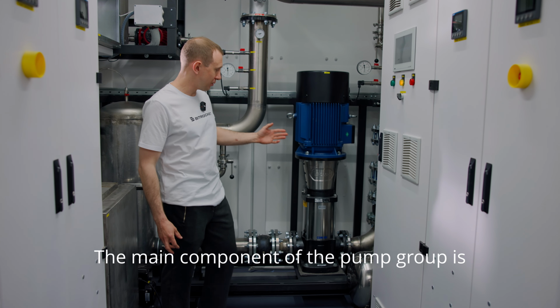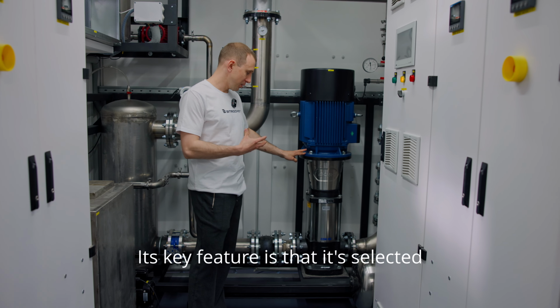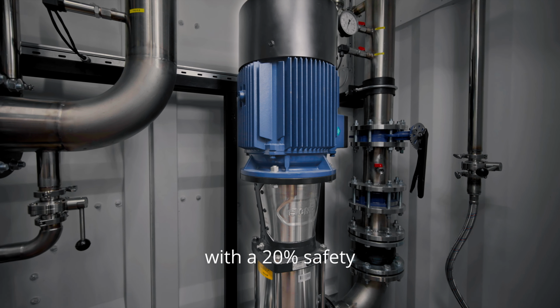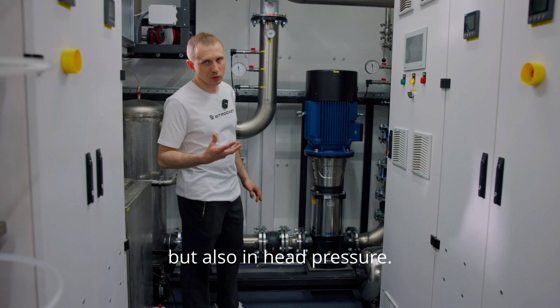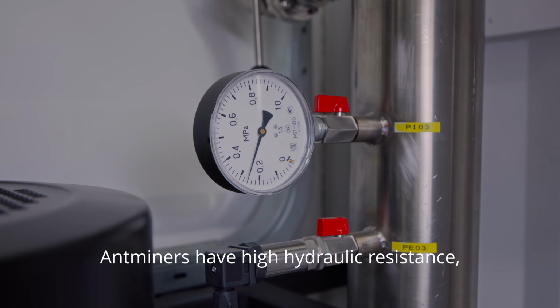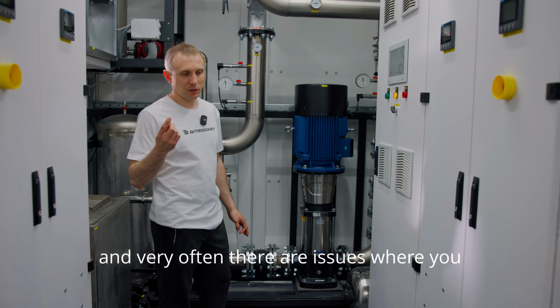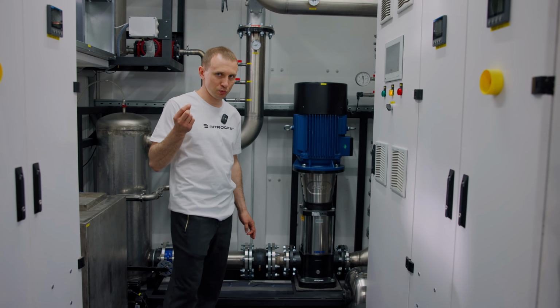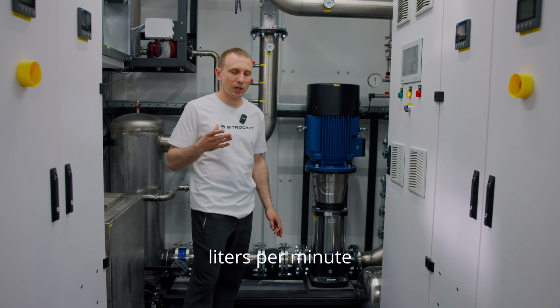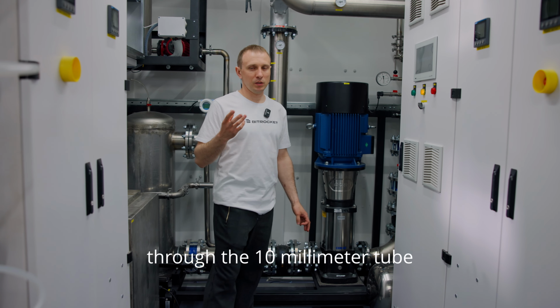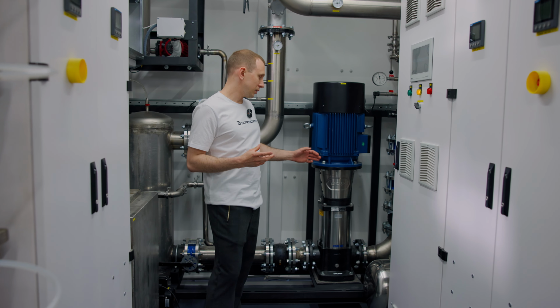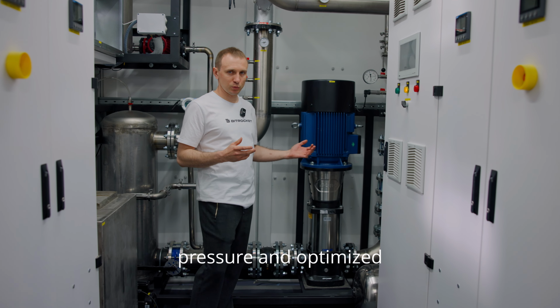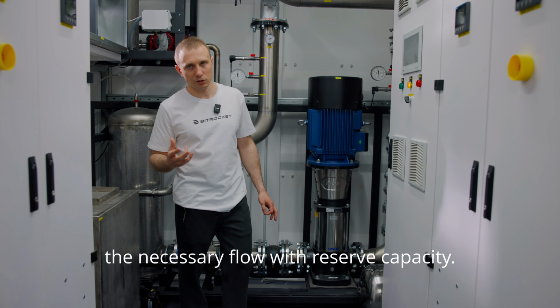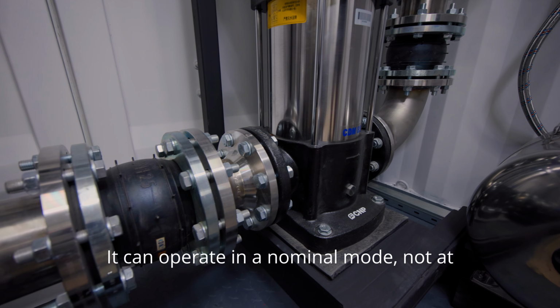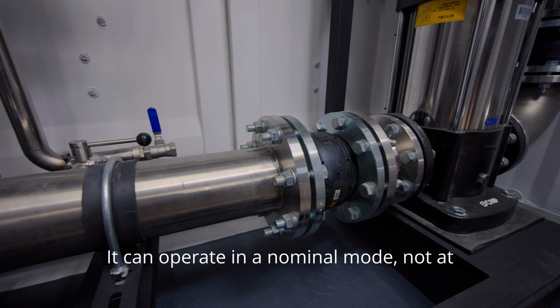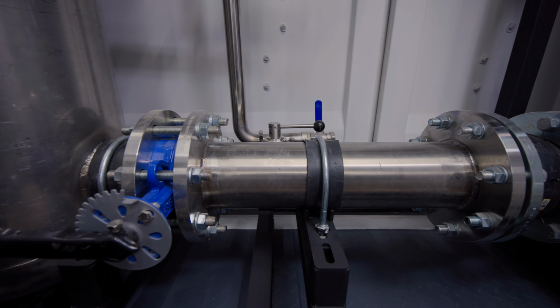The main component of the pump group is the circulation pump. Its key feature is that it's selected with a 20% safety margin, not only in flow rate, but also in head pressure. Antminers have high hydraulic resistance, and very often there are issues where you can't push the required amount of water. The manufacturer recommends 10 to 11 liters per minute through the 10mm tube or the compression fitting. This pump, thanks to its high head pressure and optimized impeller design, can deliver the necessary flow with reserve capacity. It can operate in a nominal mode, not at maximum load, which increases its lifespan.